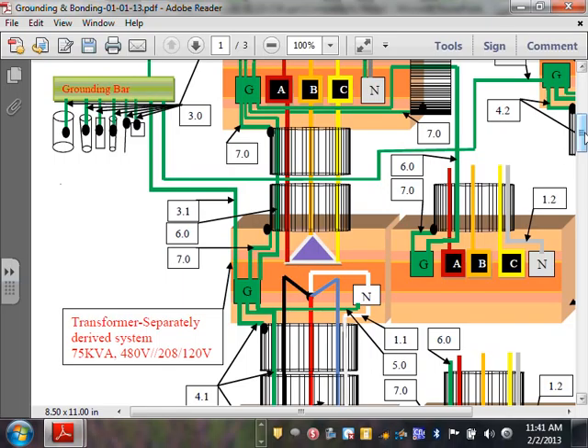I could have just run a 4-aught once between here and take care of business all in one. You're showing that number 6, combining 3.1, 6.0, and 7.0 all on one wire, and it's a 4-aught. Okay, 7 and 6.0. Is that one? So not bonding the building steel, what you're saying. No, you can't do that. Not bonding to the steel. You cannot do that. Got it.